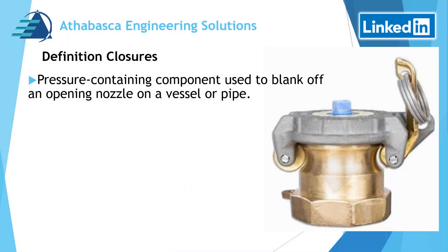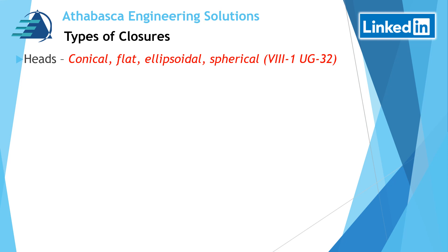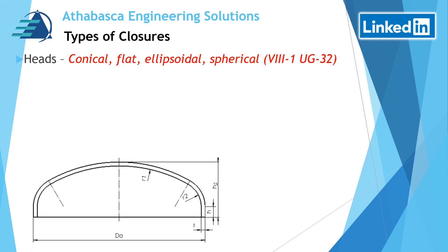The definition of a closure by ASME is a pressure containing component used to blank off an opening nozzle on a vessel or pipe. Closures are grouped into categories. The first group is called heads — conical, flat, ellipsoidal, and spherical heads are common examples, as shown in the diagram below, referencing Section Eight, Division One, UG32.